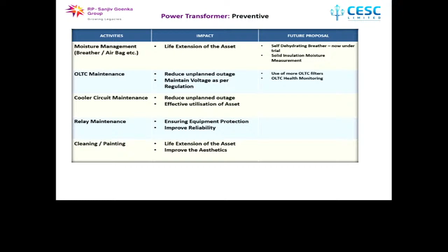One major periodic maintenance we carry out with the power transformers is OLTC maintenance. We have all the power transformers fitted with OLTC. Due to strict regulatory mandates and statutes, we have to maintain the voltage within a band, so we have to use OLTCs in our transformers.